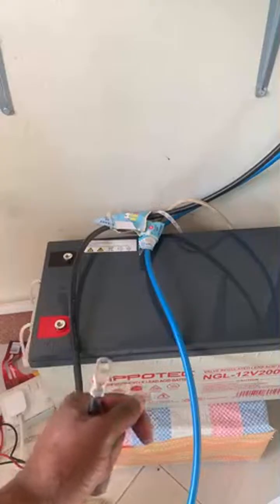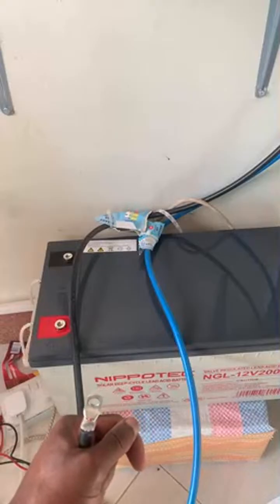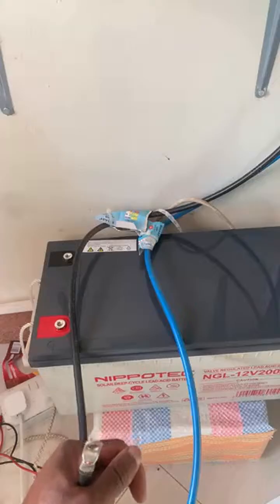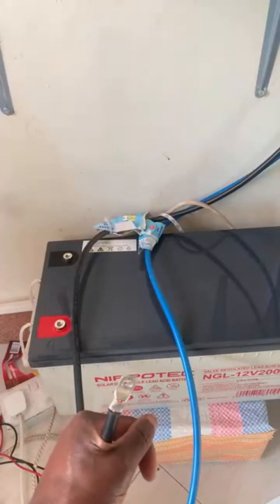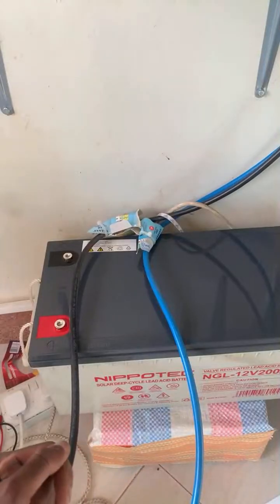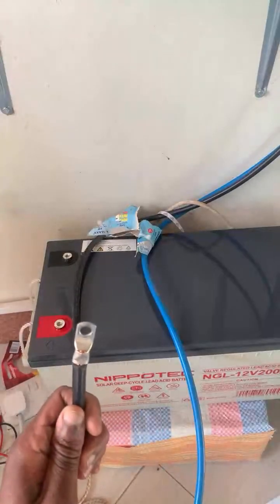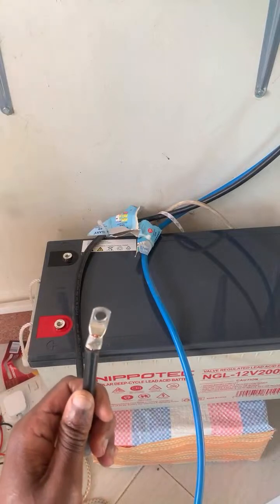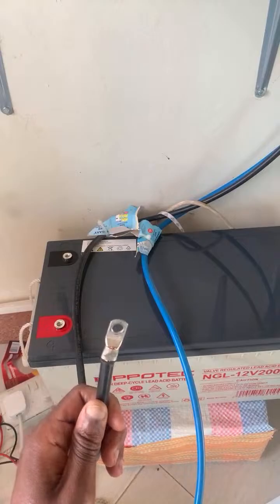Daniel Elegant says, Top Boss, please explain why we have reading from the inverter while it's not connected to any form of power. Absolutely. Now, an inverter has capacitors. Those capacitors that were connected in parallel are the ones that are discharging slowly. So before I reconnect to the battery, we will also take the reading and establish. Previously, it was around 4.5. We'll see, is it completely discharged to zero or what? But that is a very good question, Daniel Elegant. Why do we have voltage coming from the inverter yet there is no source of power?